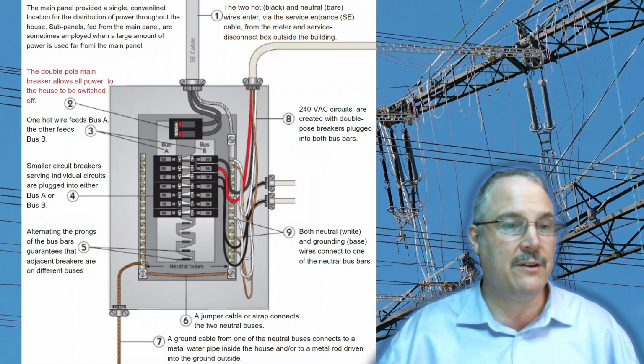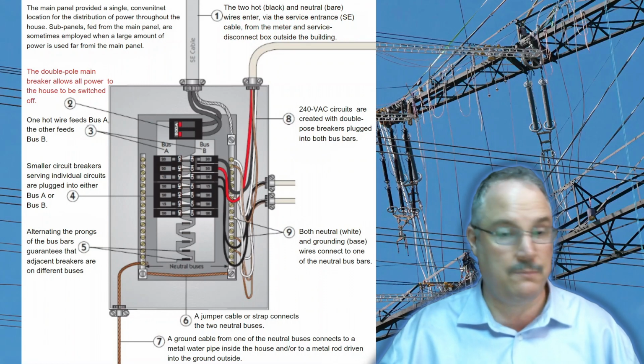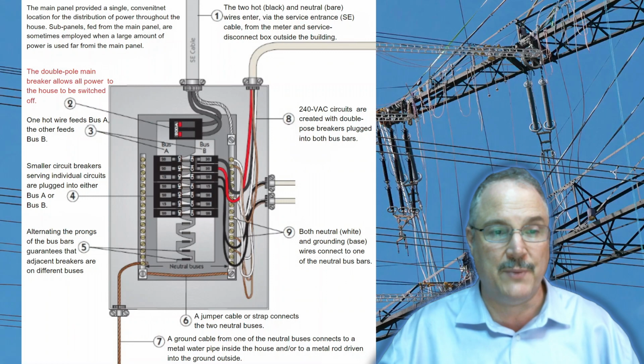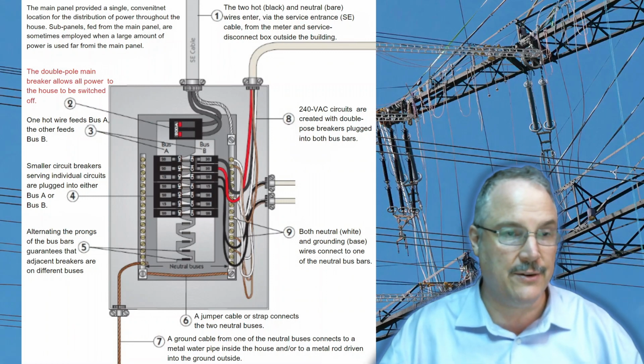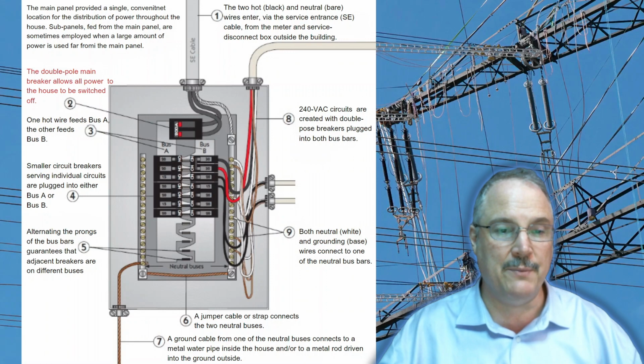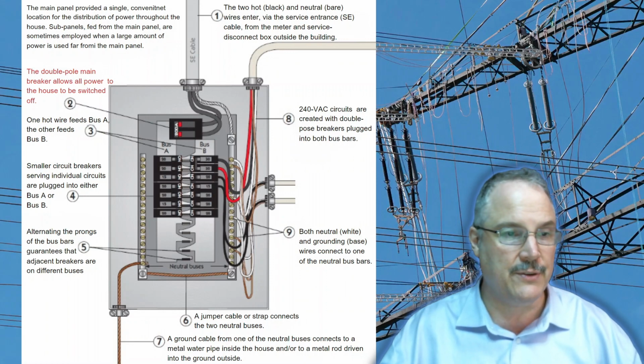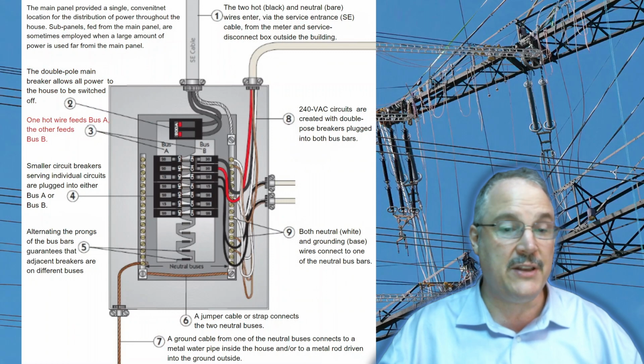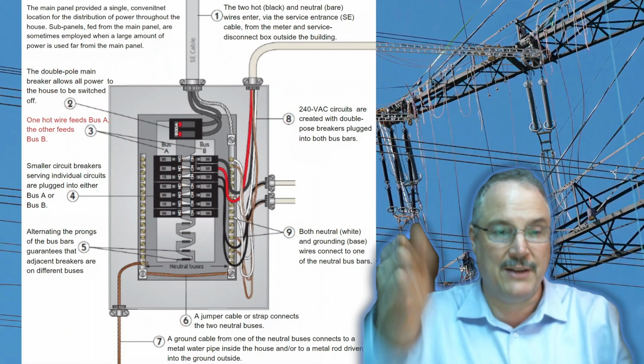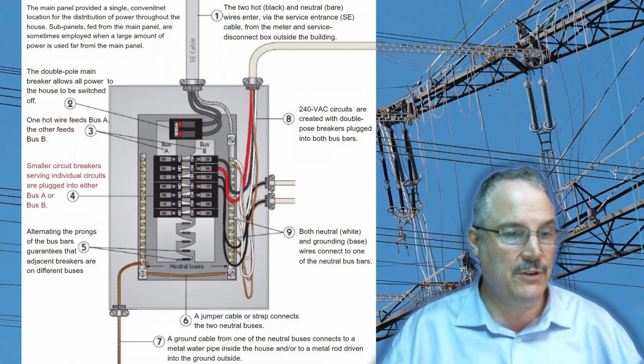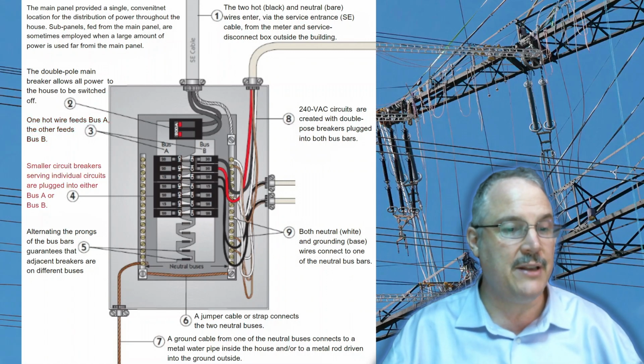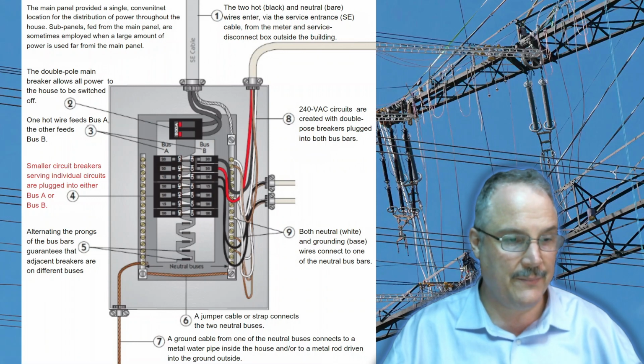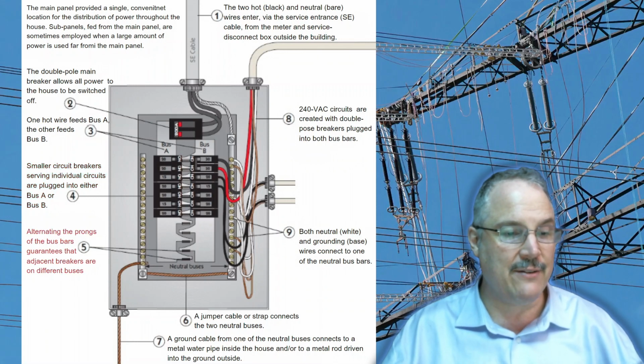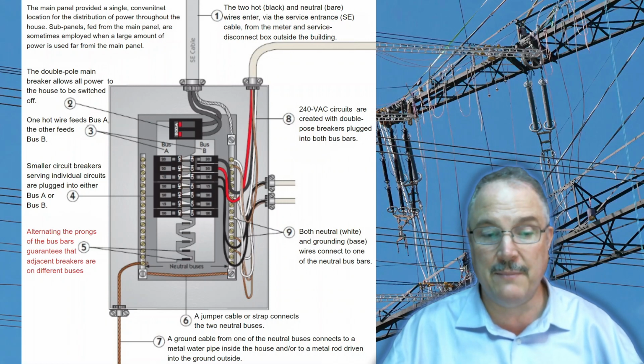The double pole main breaker allows all power to the house to be switched off. It's usually right there on top. I don't know if there are ever any exceptions, but it's a two pole. You can see them attached together. It may or may not be labeled, but it's sitting there on top independent of the other breakers. One hot wire feeds bus A and the other feeds bus B. So the box is split into two buses, as you can see, A and B. Smaller circuit breakers serving individual circuits are plugged into either bus A or bus B. Alternating the prongs of the bus bars guarantees that adjacent breakers are on different buses. I'm not sure why they do that, but my suspicion is to keep the electrical current pretty isolated from each other.